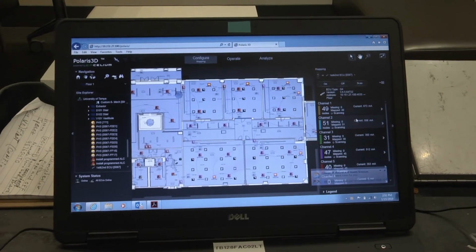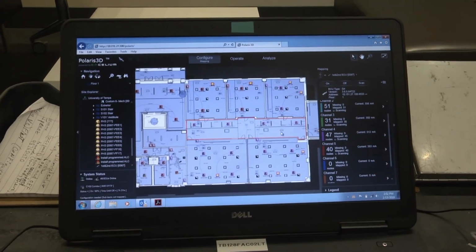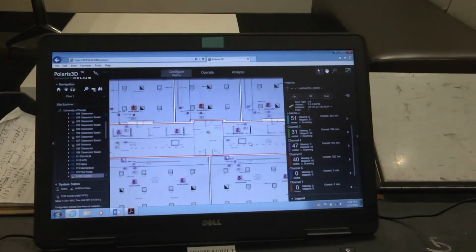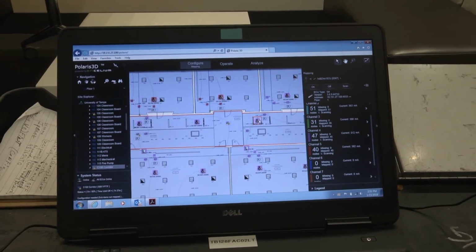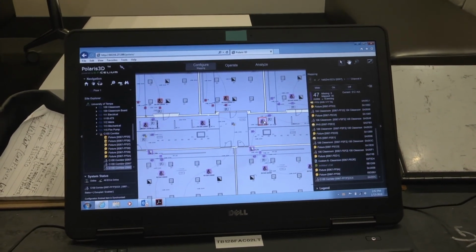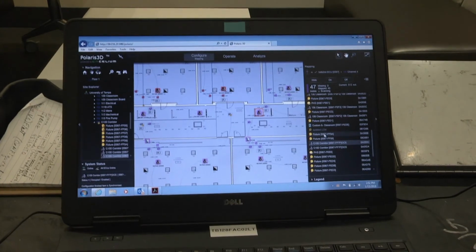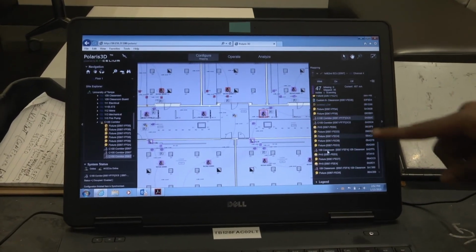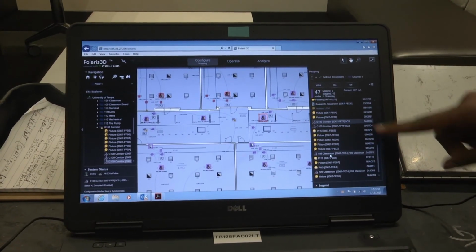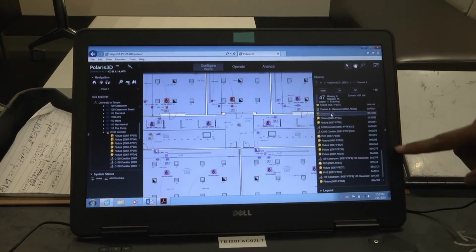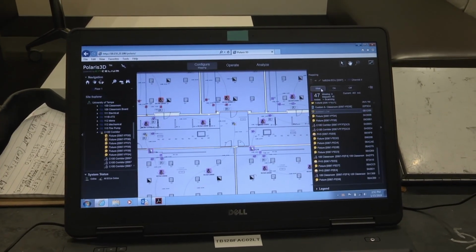All right, let's zoom into the space here. You can double click on that space, zoom to it, click on any device to get a reference point. It's purple, so it's going to open the purple channel, which is channel number 4. And then you scroll to the LCM that's shown. Where is it? The one is unmapped. Is it this? Yep. And click on the wink button up top there.